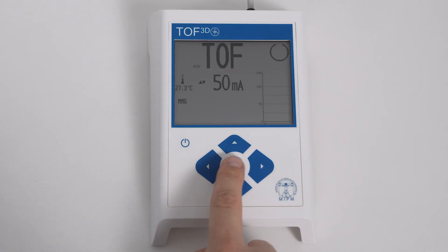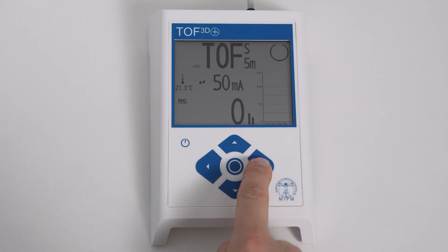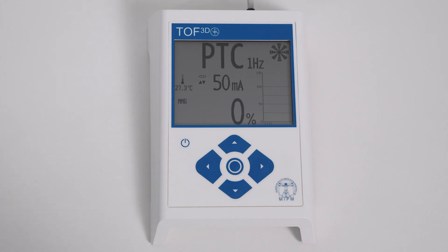Post-Tetanic Count (PTC). If the TOF count was zero, use PTC to evaluate the deep neuromuscular block. Start PTC by pressing the center key for one second. After a successful pretest, the PTC starts. After a successful PTC, the monitor goes back to TOF mode.